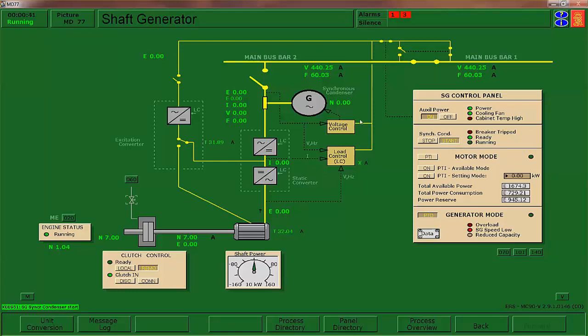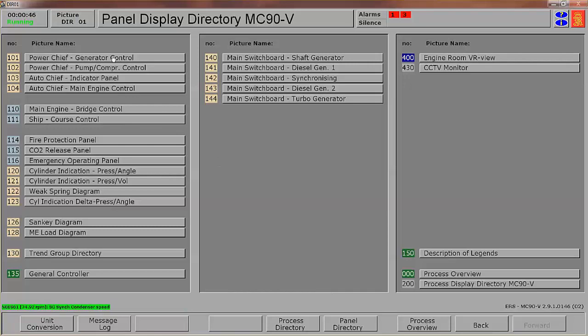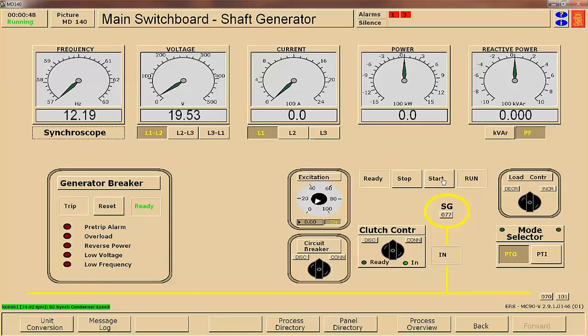As soon as you hit the start button, you'll see RPMs coming up here. If you go to the panel directory and go to shaft generator, you'll see the run light flashing, which tells you that the synchronous condenser is in the process of coming up and being available. Go ahead and, for the shaft generator, set your excitation to about 50%. I know from experience that that will get you close to 440 volts.